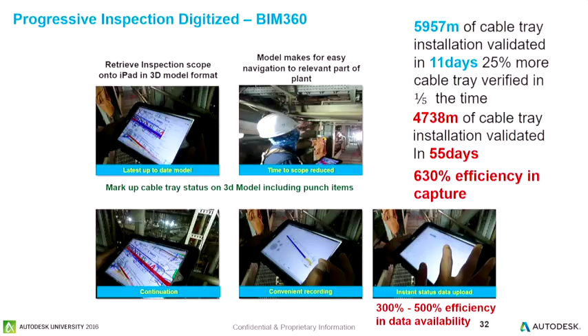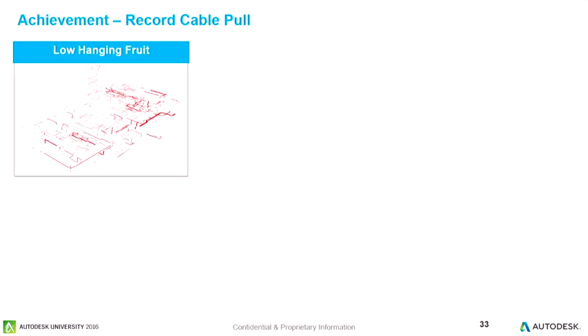So the achievement of record cable pull came down to a number of factors. Because of the granular level of punch status we were able to capture, things like this graphic were trays that were installed but just missing bolts. So we got out there with all the lower tier subcontractors, walked with them, and just put the bolts in. Low-hanging fruit gave us numbers very, very quickly.